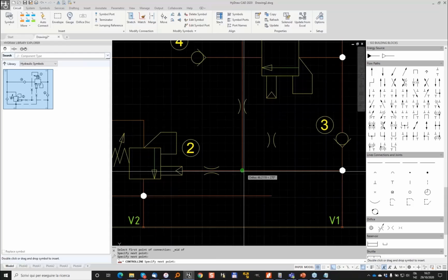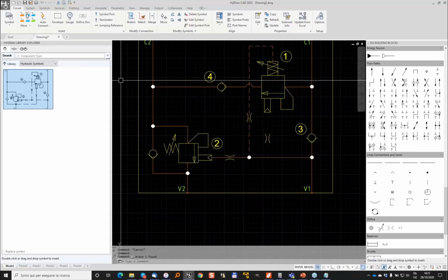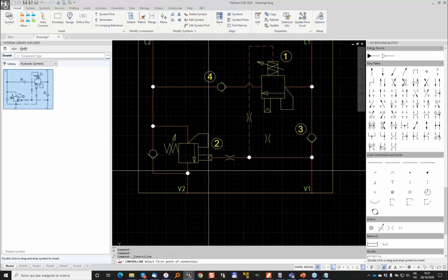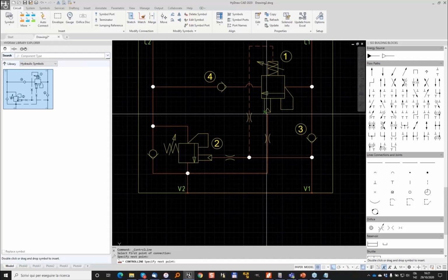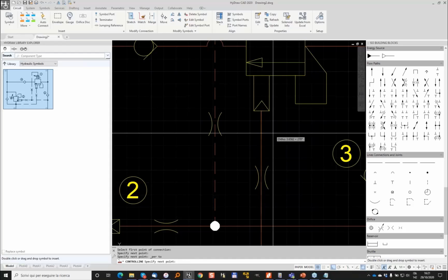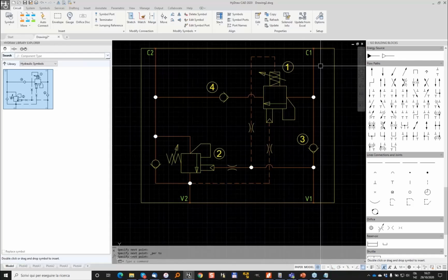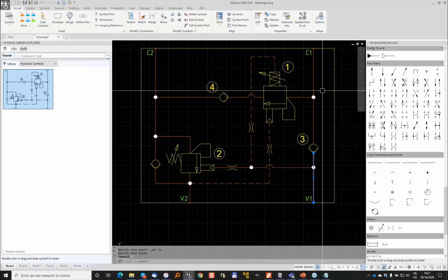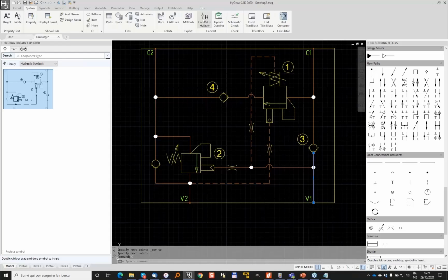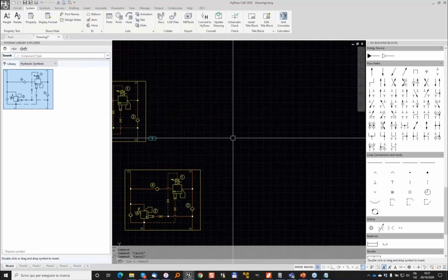And here also we can make, this one was a pilot line, so let me make a pilot line starting here, and we go Shift right click perpendicular here. So as you can see, in this case, I used the HyDraw connection line, and I used the functionality available in the convert to HyDraw to transform entities into connection line. This is applicable to any geometry that you import, DWG, DXF, whatever. Even geometries that you can just draw.